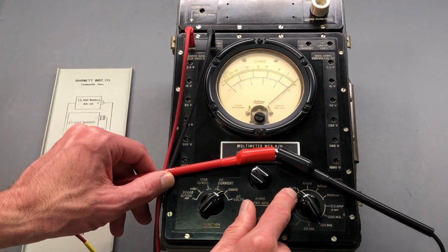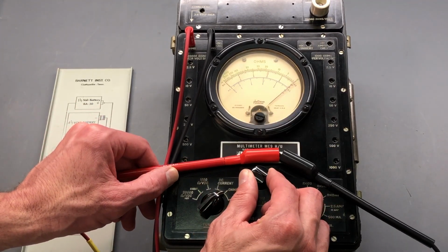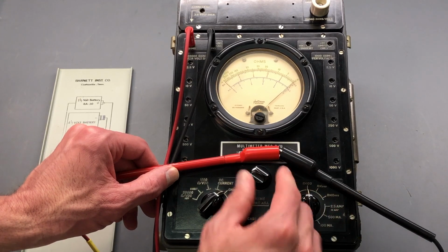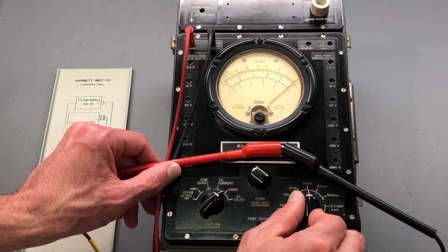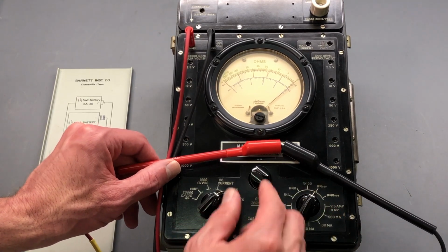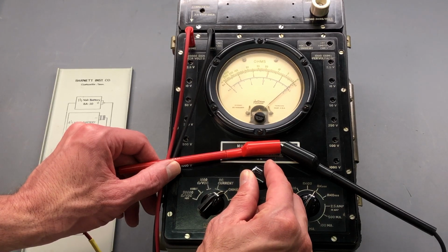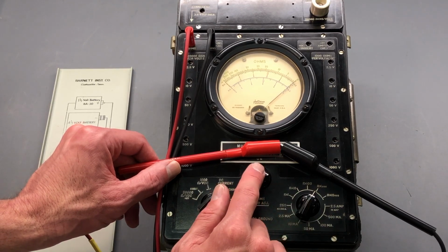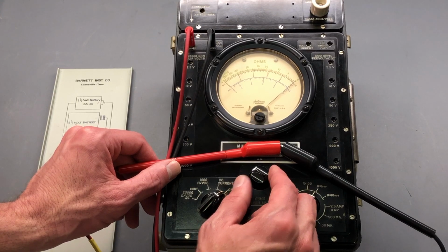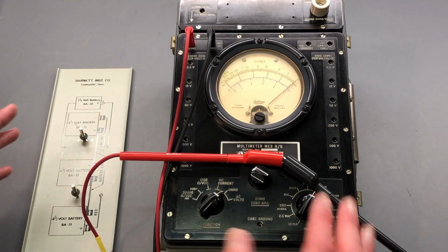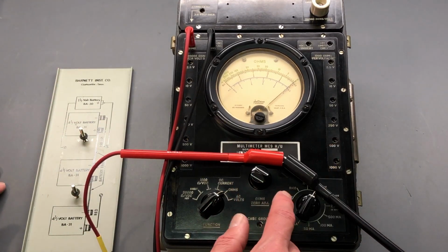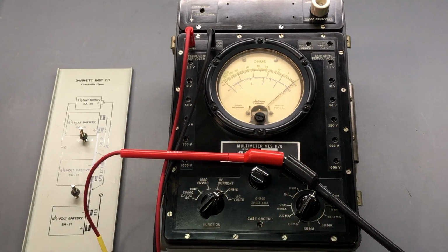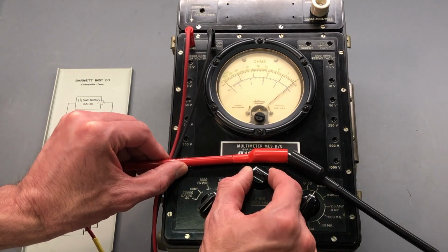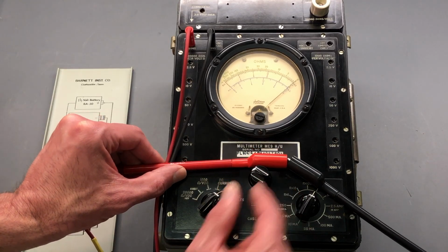If you go to R times 10, it's very close. Times 100, a slight adjustment there. R times 1000. It's normal to need to re-zero this on each range. It's just a side effect of the different tolerances of the resistors in that circuit, slight differences, so every time you change this, a slight readjustment is normal.